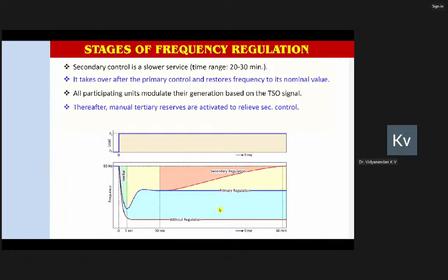So I repeat once again, it has two major stages, that is the primary control and the secondary control. Under the primary control, there are two stages. One is the inertial control, that is releasing the kinetic energy, and second is the governor action. Because of the fall in speed, the governor will come into action, extra steam will be admitted, and it will stop the fall or rise in the speed and stabilize the frequency. But with the action of the primary governor, frequency will not return to the nominal value.